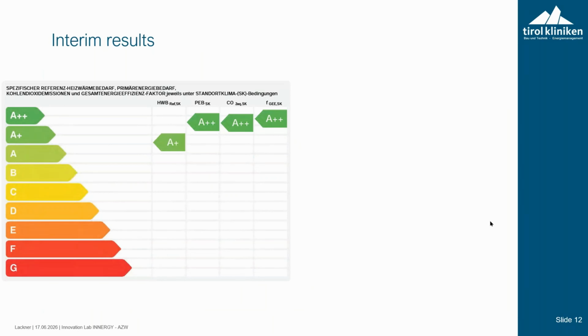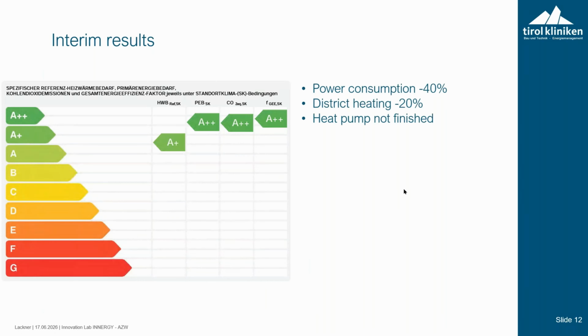What are our interim results? We were on a good way. Our power consumption got down by about 40%. Our district heating is lower by about 20%, but our heat pump is not finished yet because we have a problem with the well. We have to prepare a new deep well, and the cooling is not finished yet. So we have the problem of overheating in the offices.